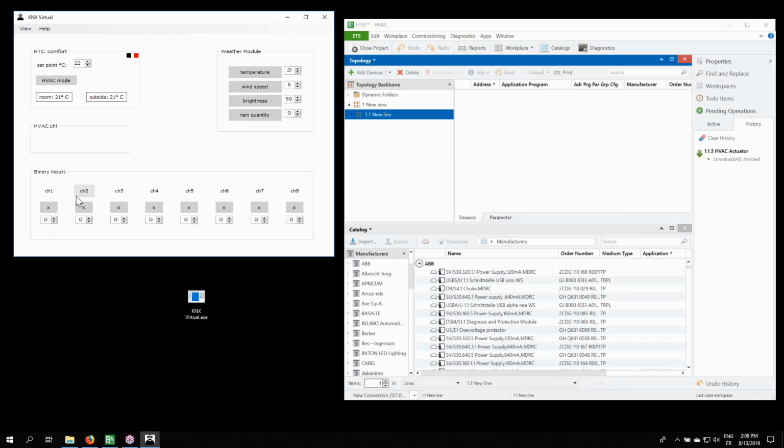But on the other hand, the building as such, so the heating installation, also needs to be protected. So that means if it would freeze outside and the window is open, then nevertheless heat needs to be added to that room in order to avoid damage being caused because of water being frozen. So that's the frost protection actually, or the building protection that will be activated because of that window contact, right? Okay, so that is actually a bit in a summary.